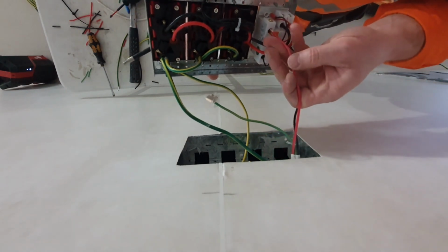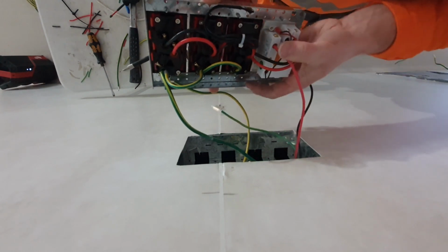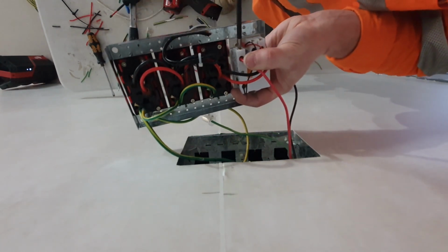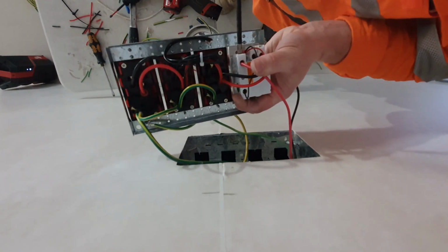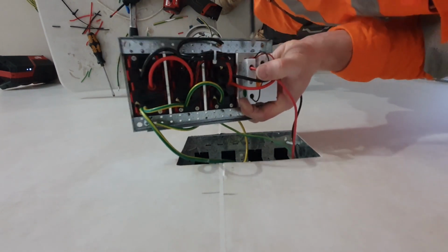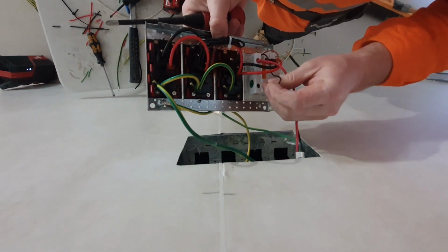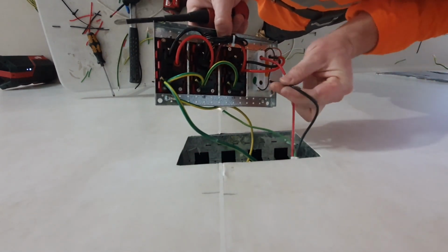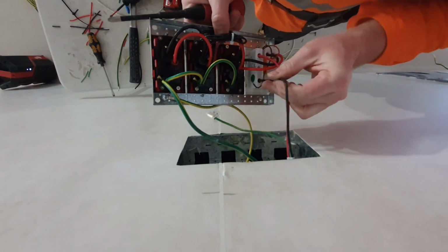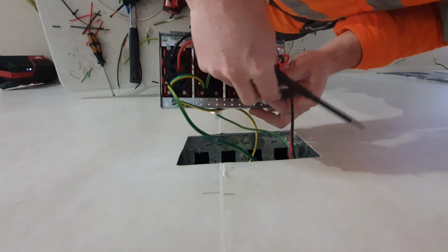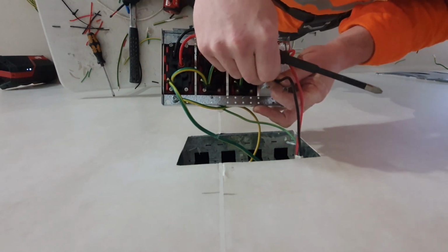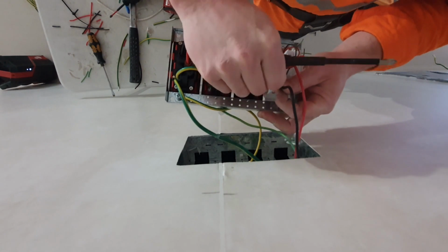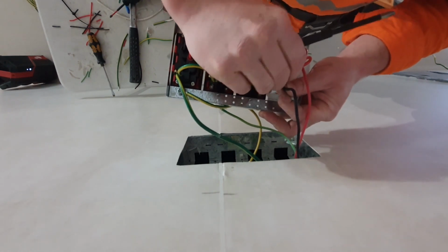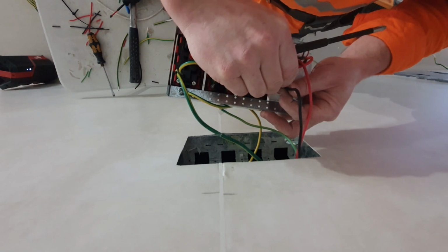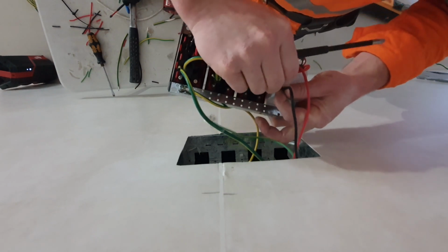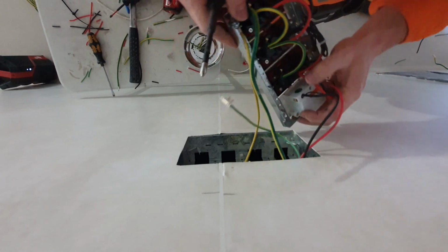So I just want to make sure that little LED cable is behind, so that when you tighten up the terminal, the 2.5mm cable in this case is getting squashed, not that little one. You don't want that little one in front even though it's ferruled, because it's going to get damaged tightening up this terminal. If you put it in behind, the screw's not going to put any pressure on it, and it's going to get sandwiched in there pretty nicely. Just a bit fiddly getting it all in.